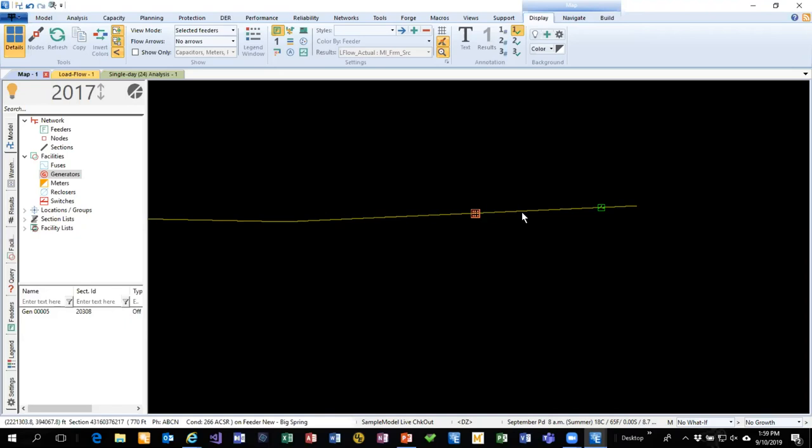I think it depends on how complex that secondary is. So if you have a single long secondary that feeds just a few customers at the end or along the route, then I think you could easily use the current secondary model for the ELV system. If you have perhaps a more complex one where you've got a few spurs and you really want to understand what the flows are like on that, then I think it pushes you towards having a more detailed model. Is there anything you want to add to that, Larry?